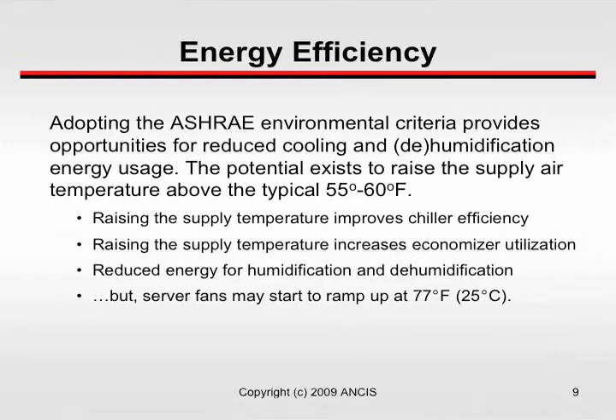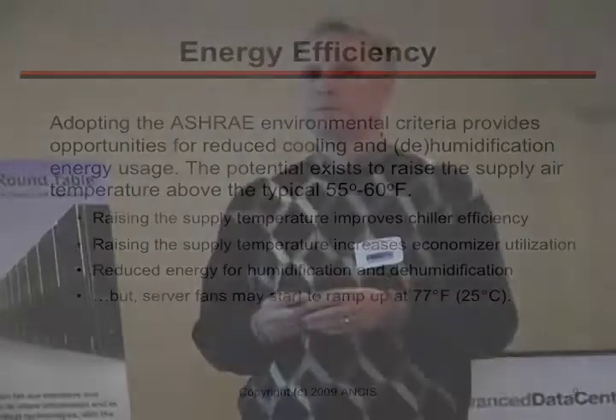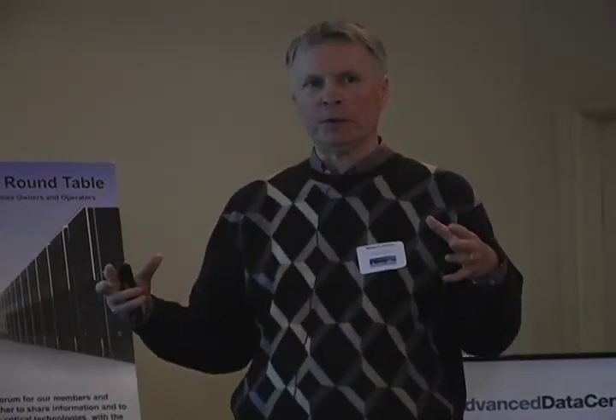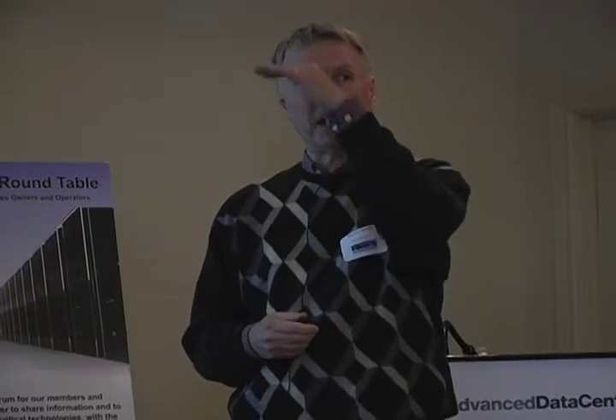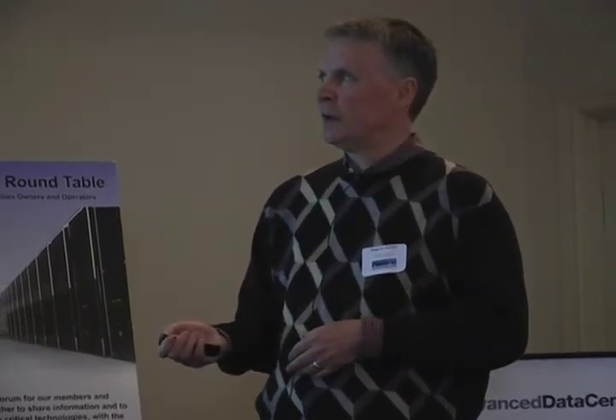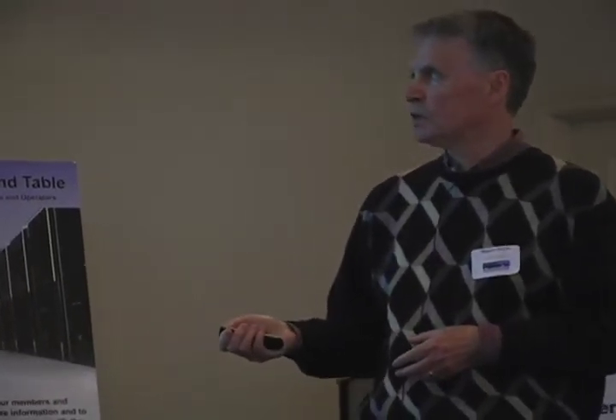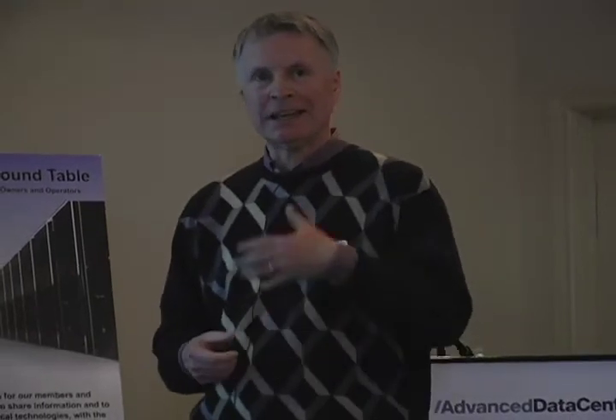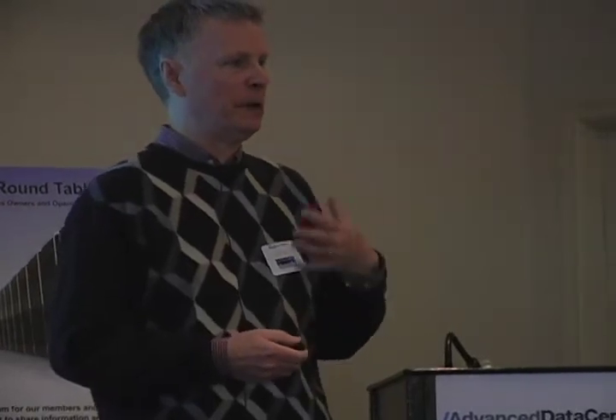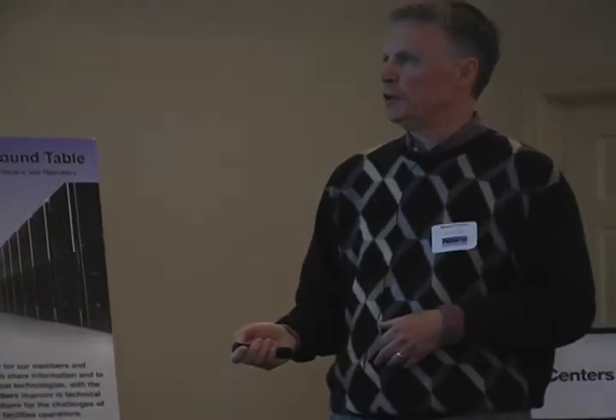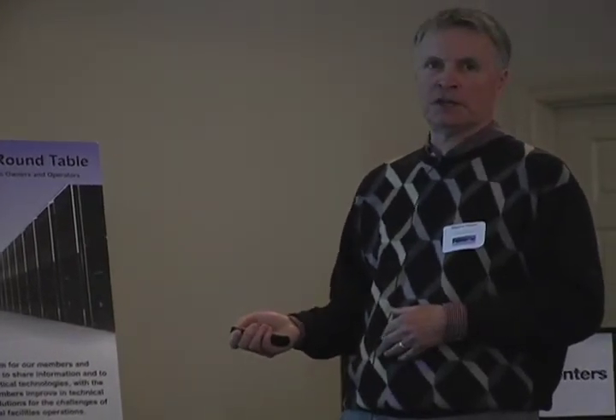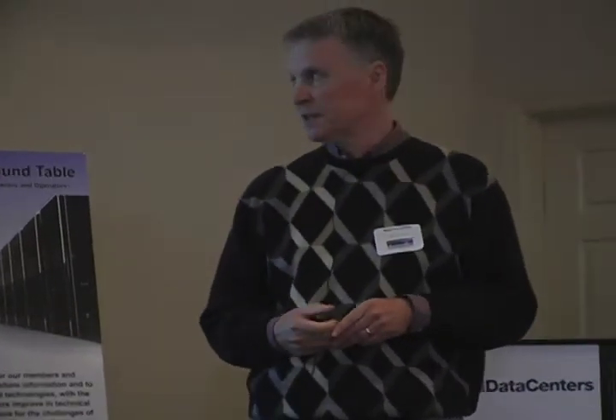Today, many data centers operate with a supply temperature of 55 to 60 degrees Fahrenheit. And if these ranges you are supposed to operate within are wider, or you can operate at a higher temperature, you can raise the supply temperature, and you will then improve chiller efficiency. Raising the supply temperature also increases economizing utilization. And ADC's data center, they have, or they will have, an air-side economizer, and that will really be impacted by this wider range. You're going to reduce energy for humidification and dehumidification. That can be quite substantial in some data centers.